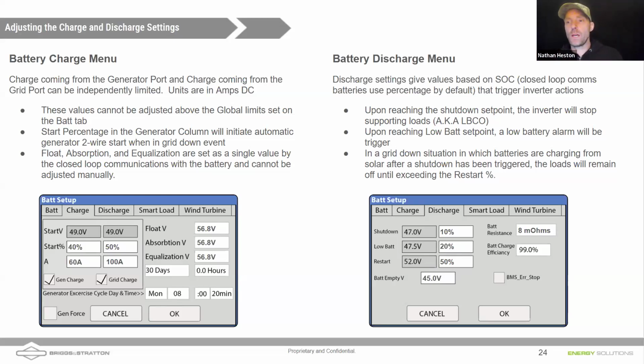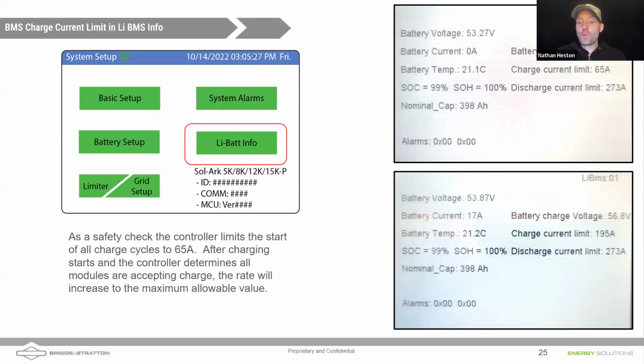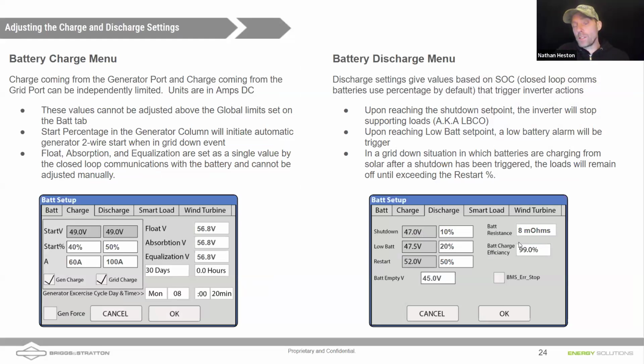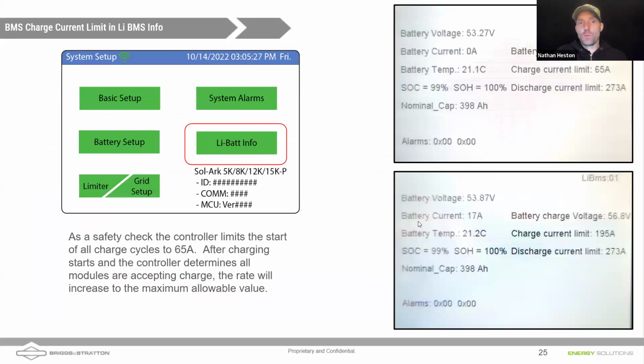It does vary a little bit, but that value is really only used by the Sol-Ark to adjust the shutdown voltage. And since our batteries are operating on a state of charge, a percentage mode, we don't actually end up using that to adjust shutdown voltage. But if you are using one of our batteries in open loop mode, this battery efficiency here can help regulate what that shutdown voltage will be.